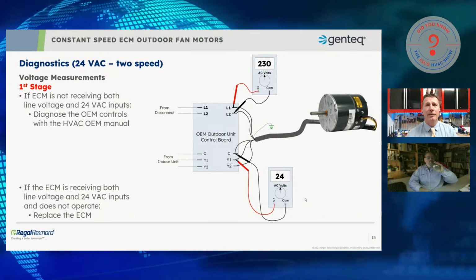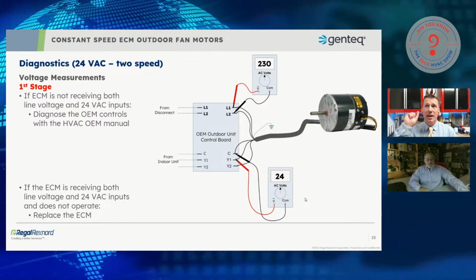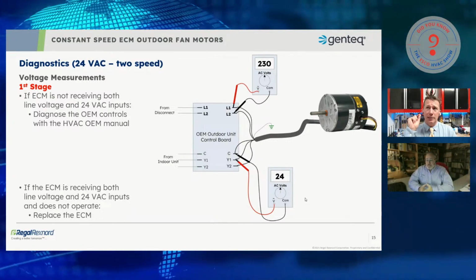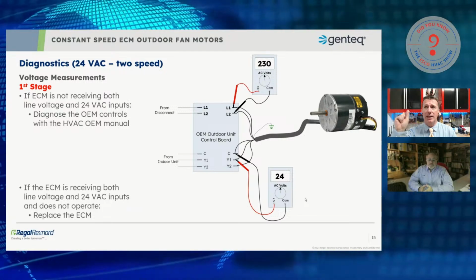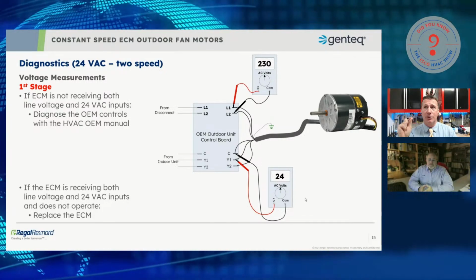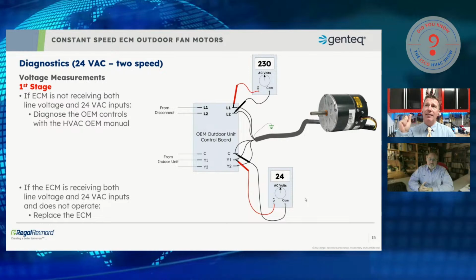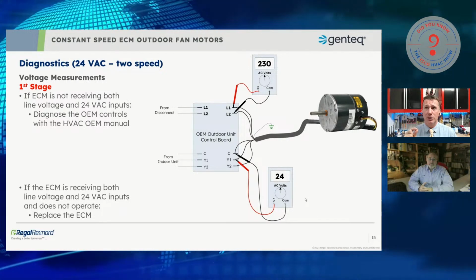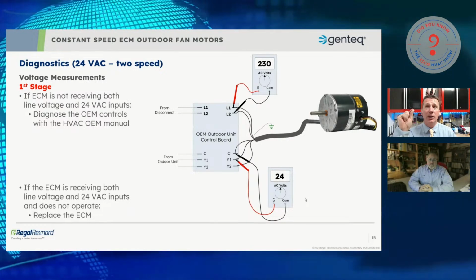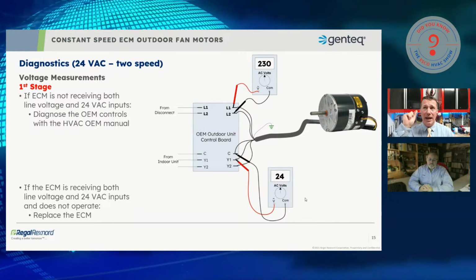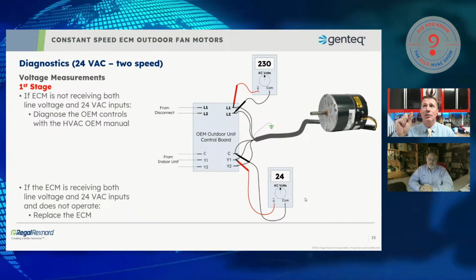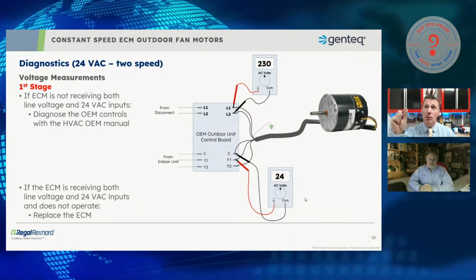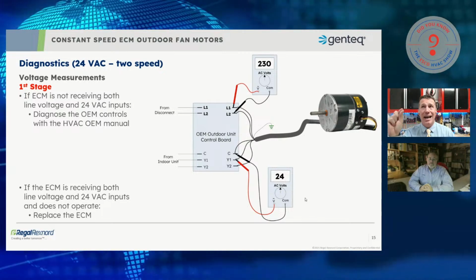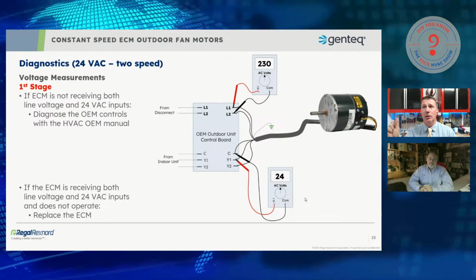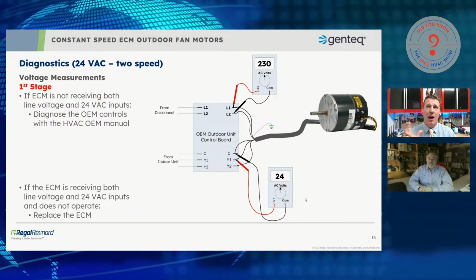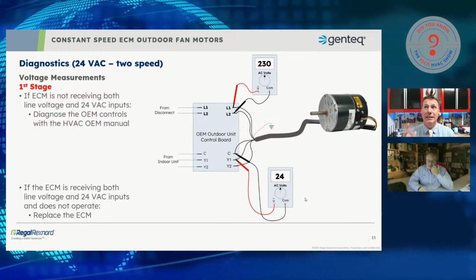No, the only thing I could think of is I can see the manufacturers of the boards utilizing relays to make the connections to the speeds for the outdoor motor so that you wouldn't have the potential for overloading your low voltage circuit for the entire system. So I could see potentially you could have a relay failed. Say you had a Y2 relay on the board that failed and you had a Y2 signal coming into the board, but not a Y2 signal coming out of the board going to the motor. So just something to think about when we're troubleshooting those speed connections.